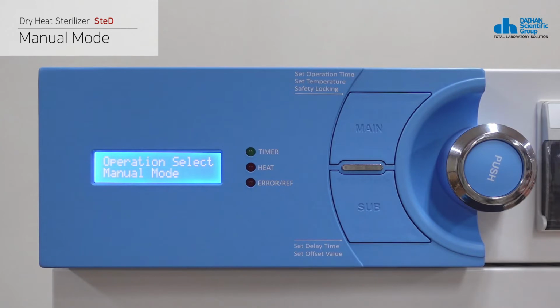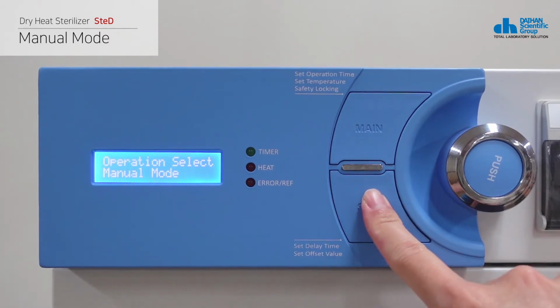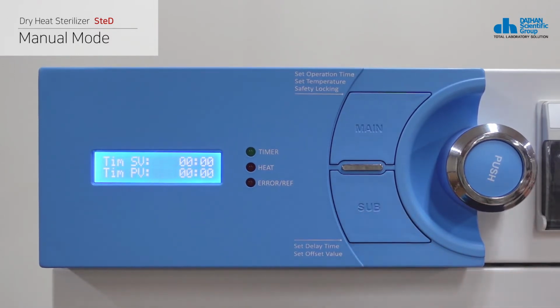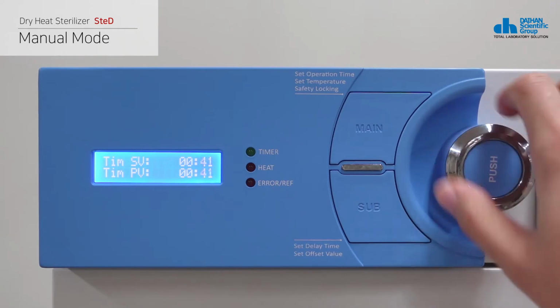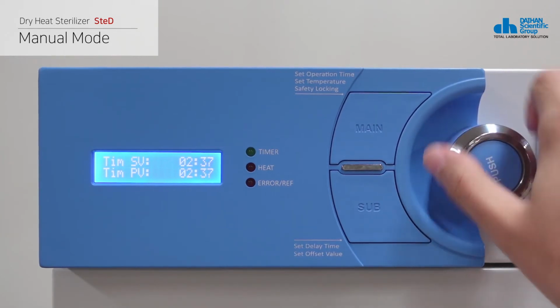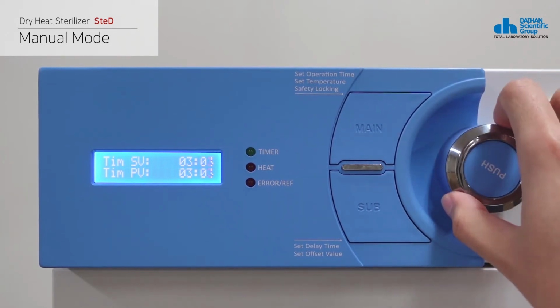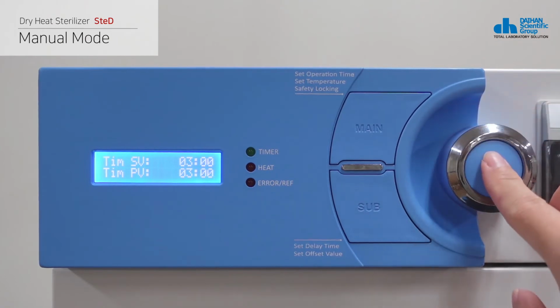Manual mode is a mode that can be operated by setting sterilization conditions as intended by the user. Depending on the user setting, it can be used as an incubator or oven in addition to the sterilizer. Press the sub button in manual mode and enter timer setting mode. Turn the knob to set the timer up to 99 hours and 59 minutes. If the timer is not entered, heating action is not performed.